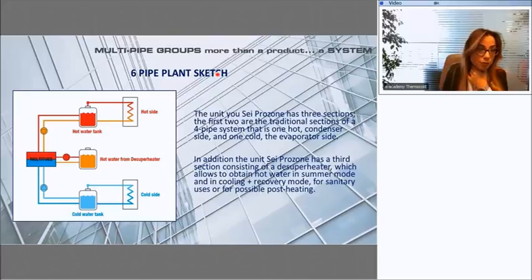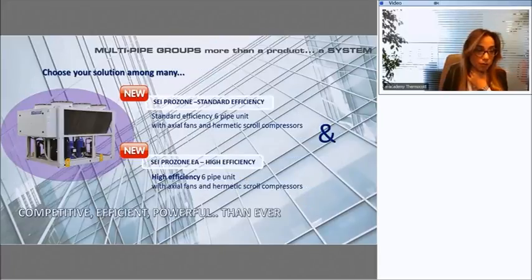We can analyze here in detail the two operating maps. In cooling mode, we are between 45 and 46 as a maximum outdoor temperature, and it is possible to produce chilled water down to +5 in cooling only mode by adding the additional fan speed modulation as an optional.